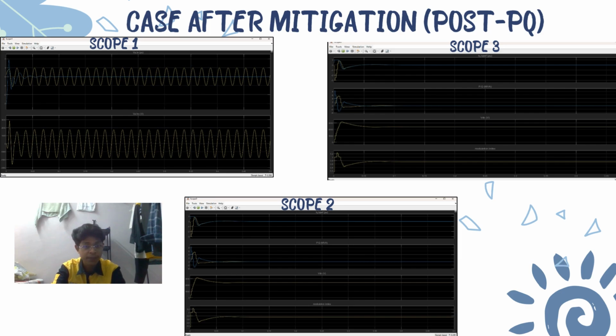So this is the last part, which is the case after mitigation, with mitigation of the voltage flicker in the system. In this part, the distribution STATCOM is switched to Q regulation mode to actively mitigate the reactive power and voltage flicker, while the load continues to fluctuate at 5 Hz. In scope 1, as we can see, it shows a sinusoidal voltage waveform and a smooth current with 5 Hz current oscillation. This confirms that the distribution STATCOM is actively compensating the reactive power in real time, keeping the voltage at bus B3 stable.